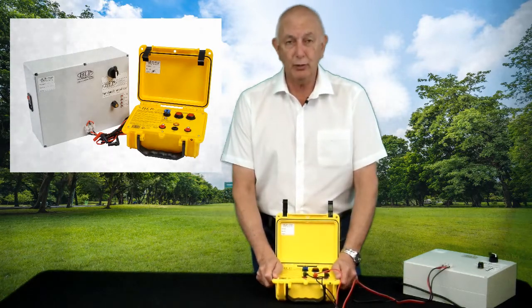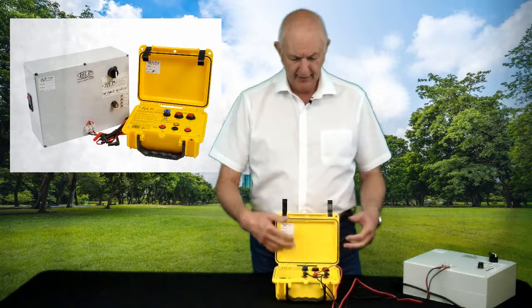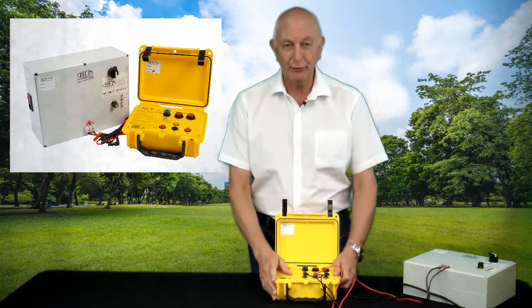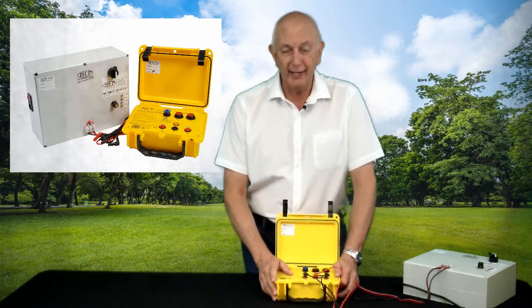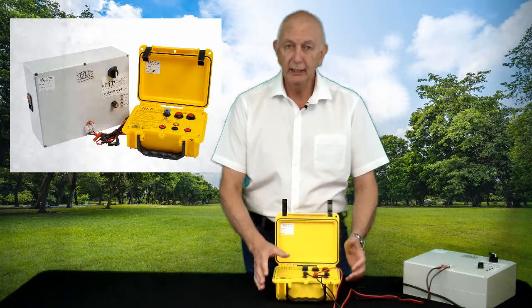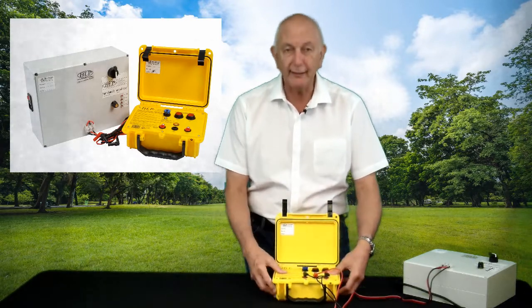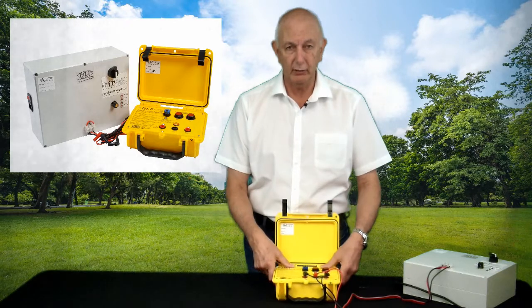Obviously, if you're going to do the annual calibration, you want to have a bit of a look at it. This is a brand new one. The ones in the field often get very dirty, so we always take that time to give them a clean and to make sure that there's no cracks in the case and the waterproofing's all working and all that.